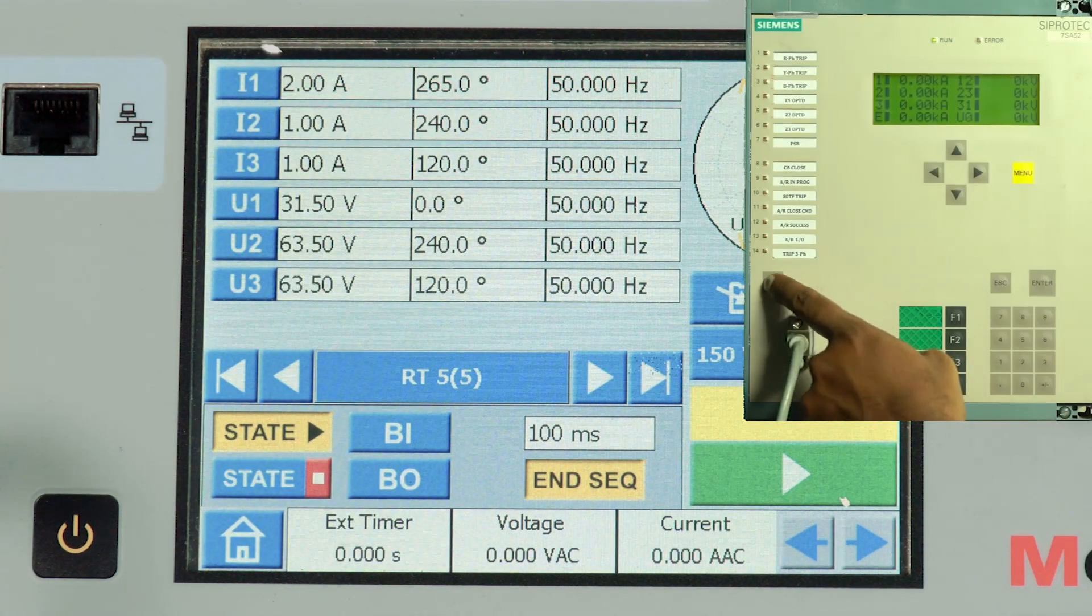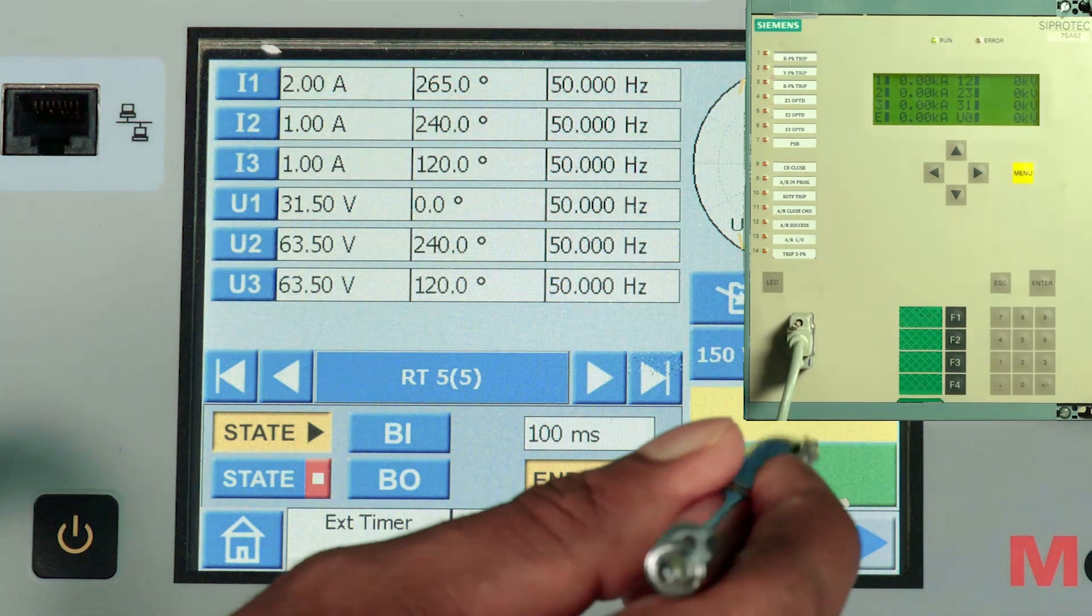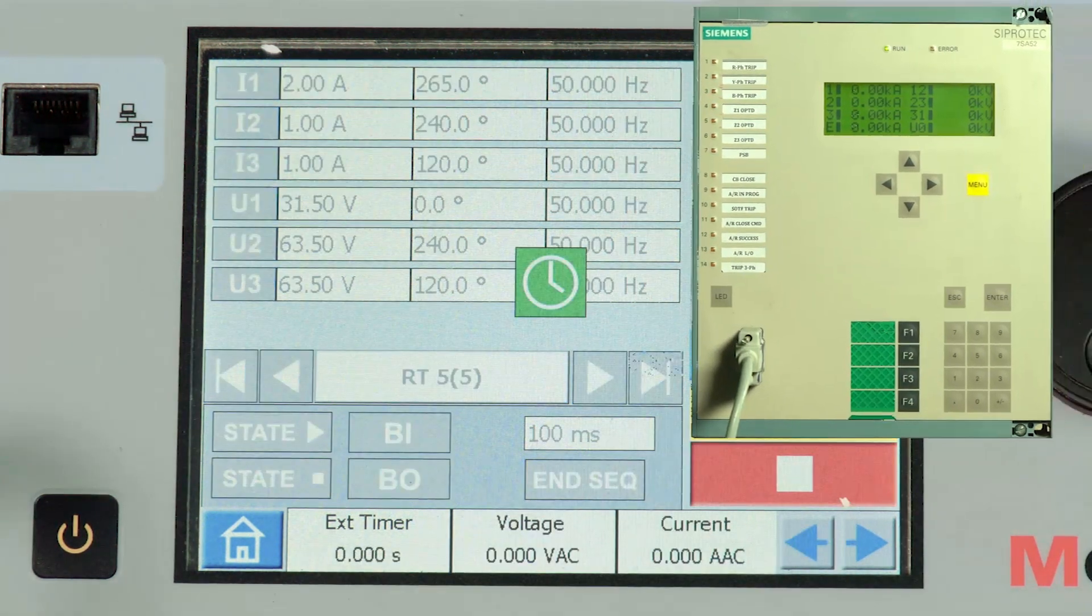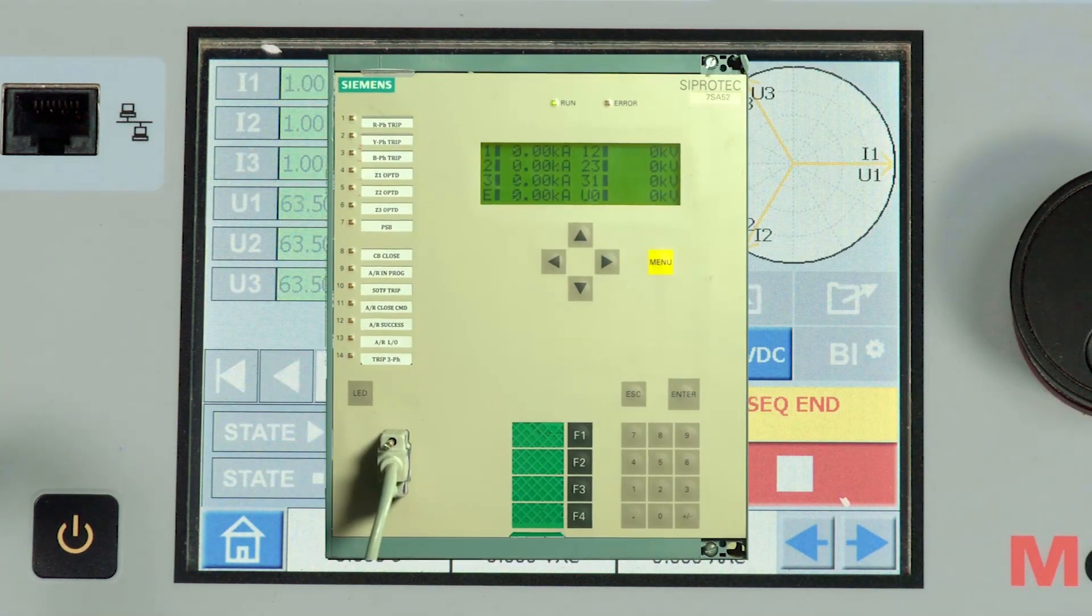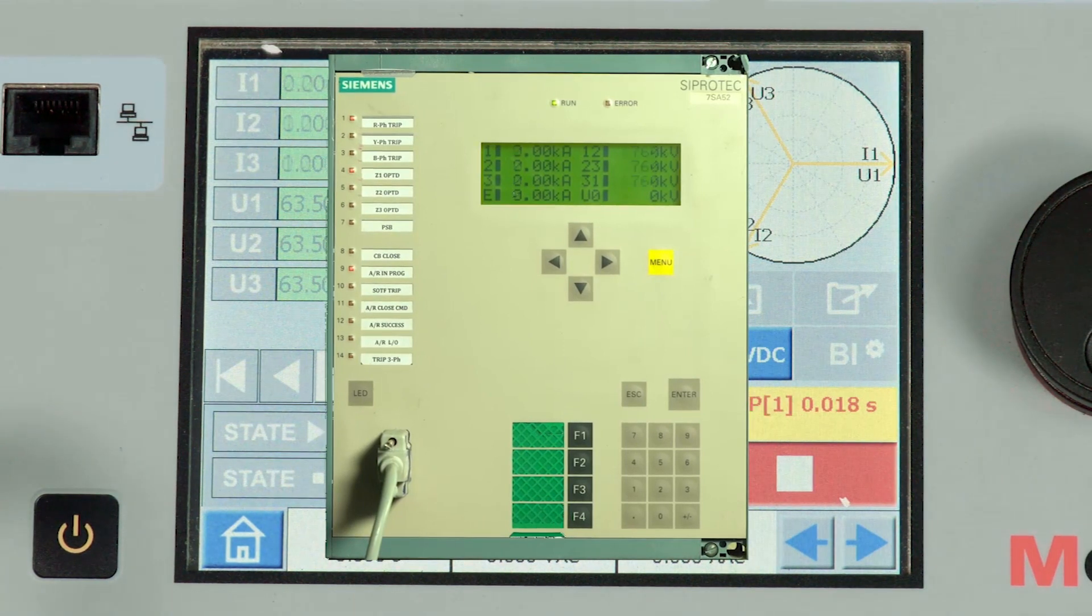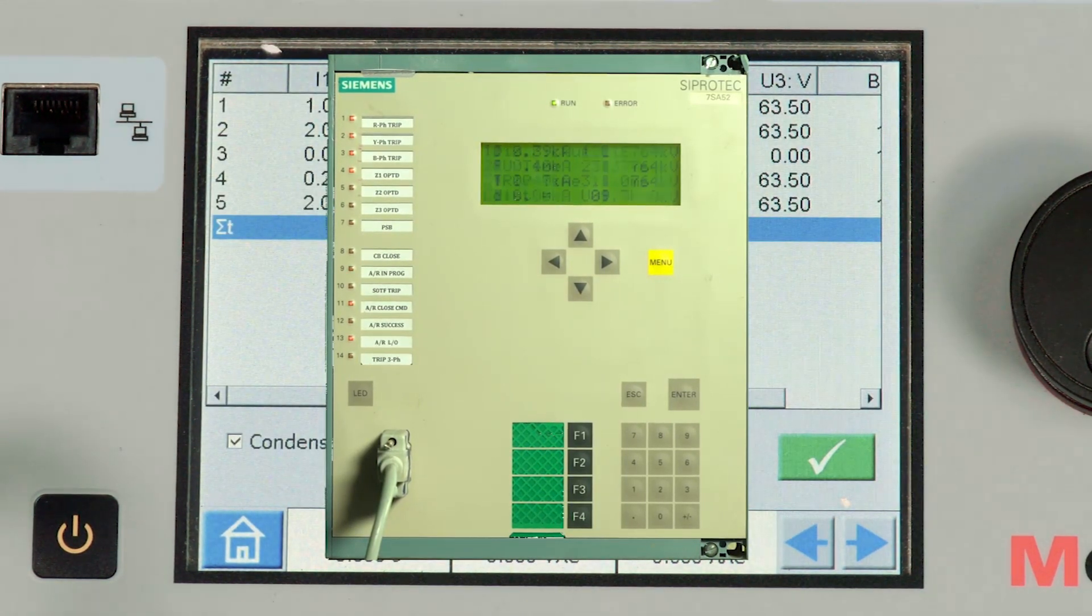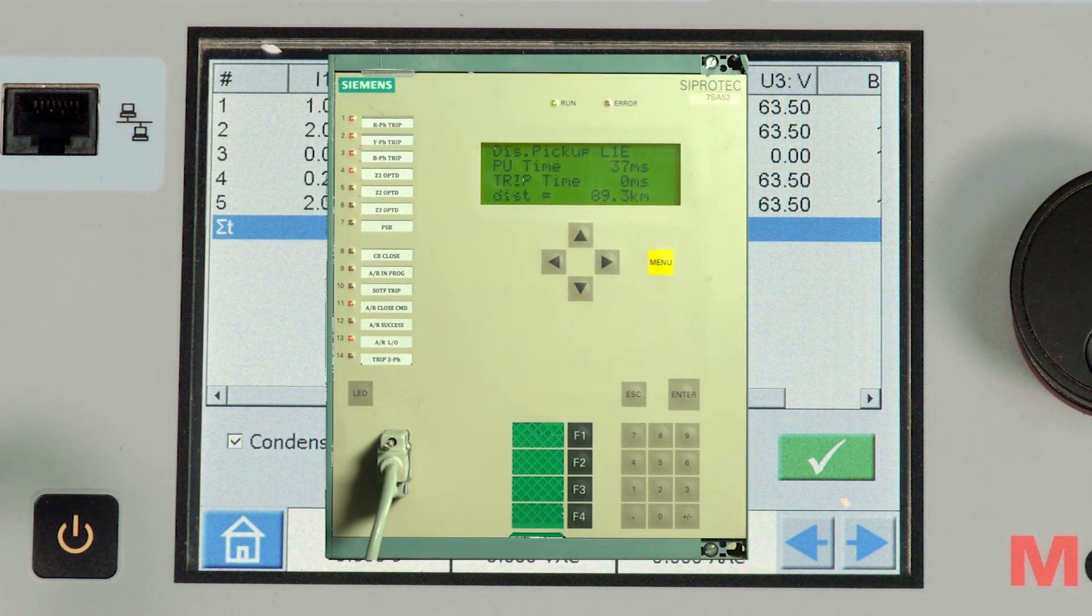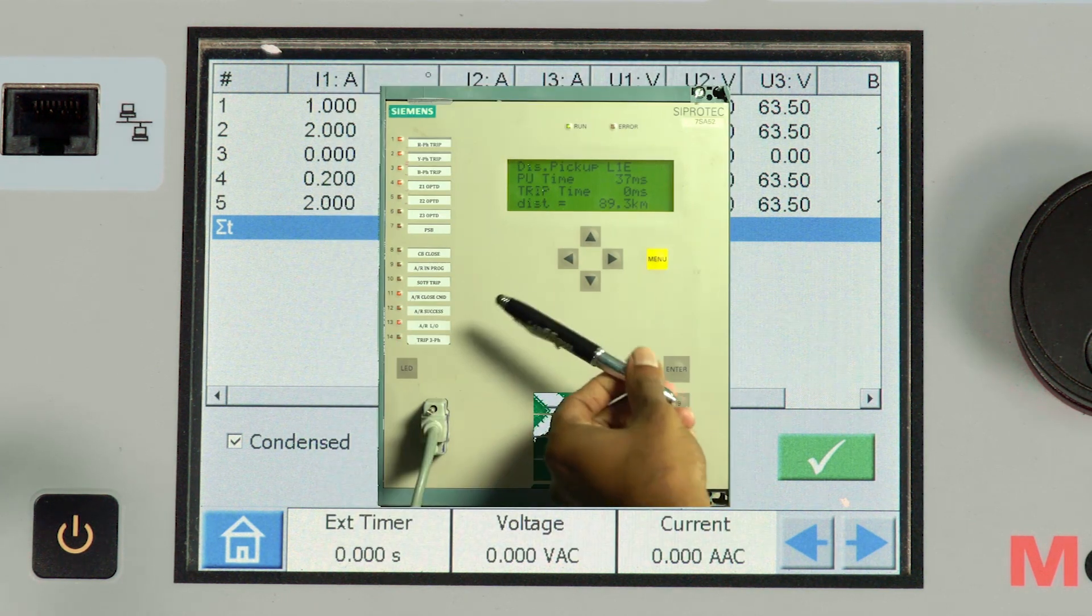Let me reset the relay and play the state. We can observe the auto recloser in progress. Then after the dead time we can see the close command and the lockout happening simultaneously.